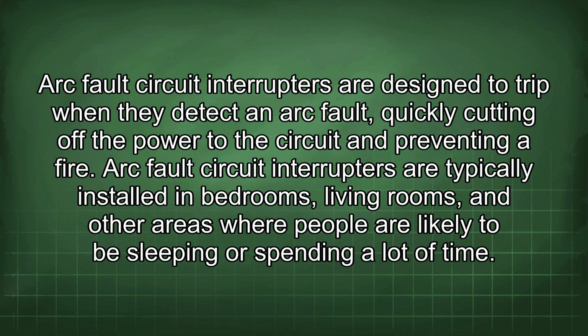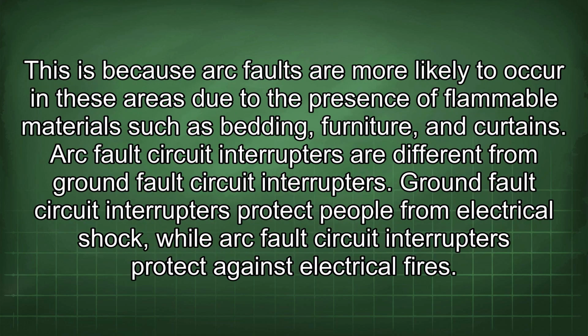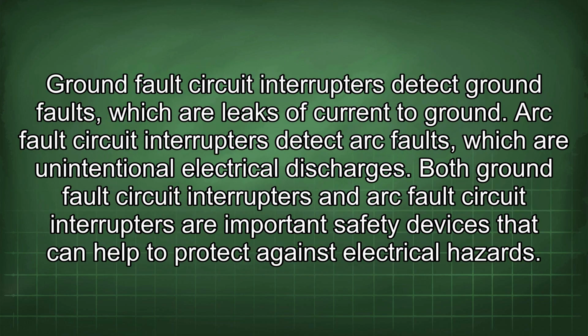Arc fault circuit interrupters are typically installed in bedrooms, living rooms, and other areas where people are likely to be sleeping or spending a lot of time. This is because arc faults are more likely to occur in these areas due to the presence of flammable materials such as bedding, furniture, and curtains. Arc fault circuit interrupters are different from ground fault circuit interrupters. Ground fault circuit interrupters protect people from electrical shock, while arc fault circuit interrupters protect against electrical fires. Ground fault circuit interrupters detect ground faults, which are leaks of current to ground.